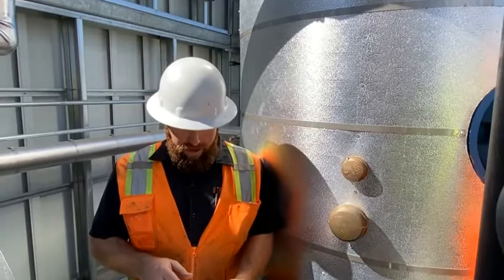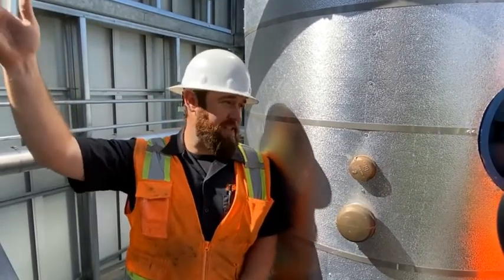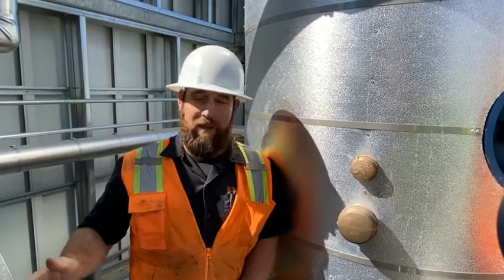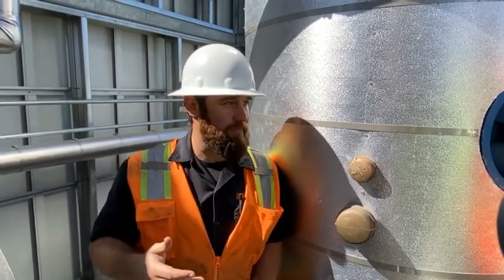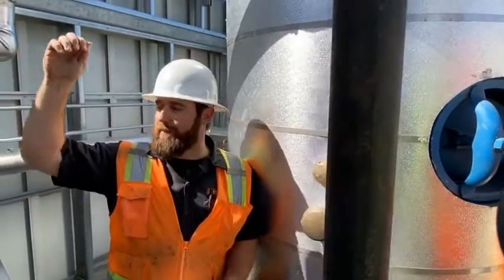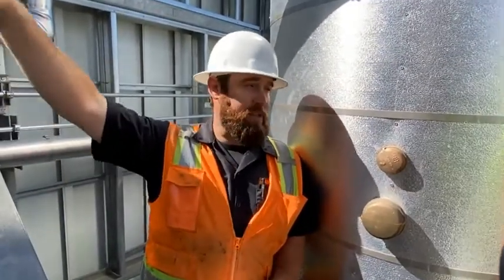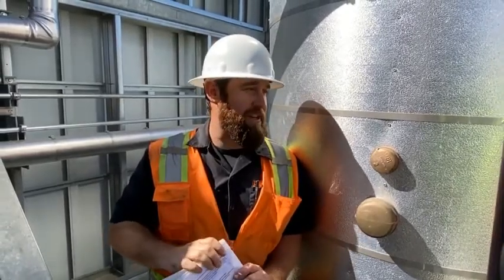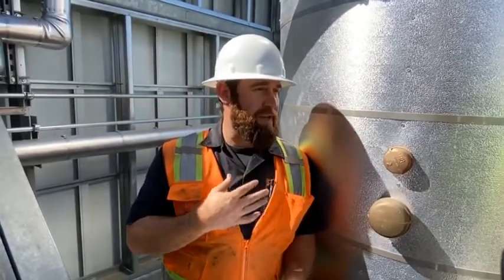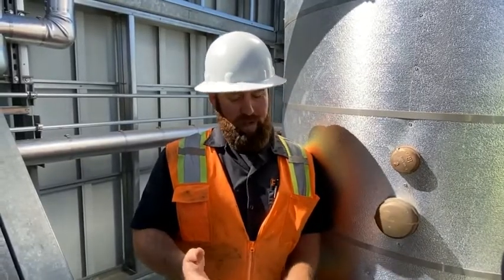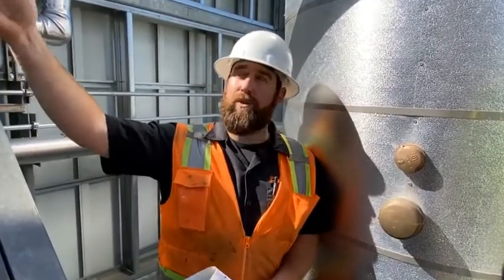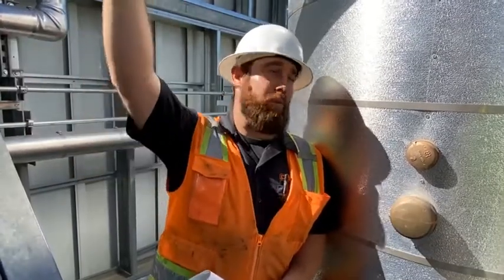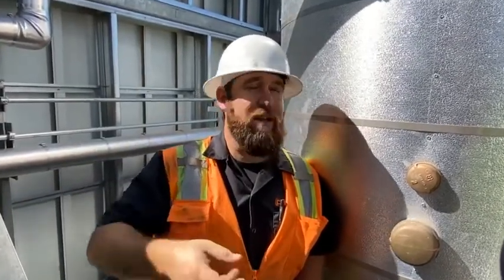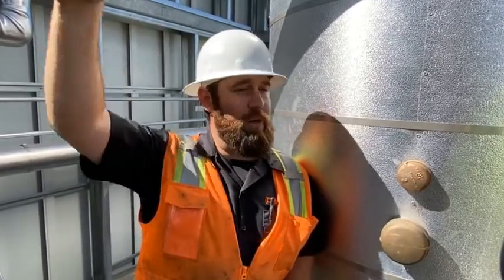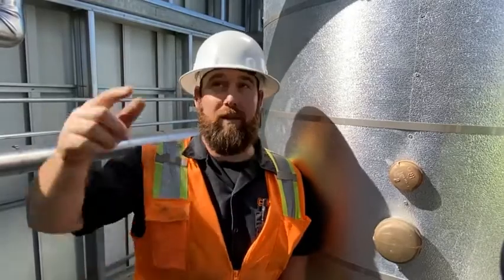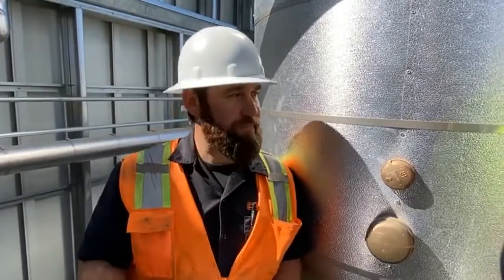For sure every year. And then it also says to check the combustion system every year as well. So these have induction fan motors? Right. Yeah. So for part of my startup, I had to check the exhaust, and there's certain levels that the manufacturer recommends. So my company does offer annual services, and that's one of the things we'll do. We'll check the combustion, make sure everything's right there. We'll replace the igniters, the flame rods, check the circuitry on the blower, pull the burner, clean out the burner, clean inside, and do all that stuff. And everything's up there. Yes, sir.